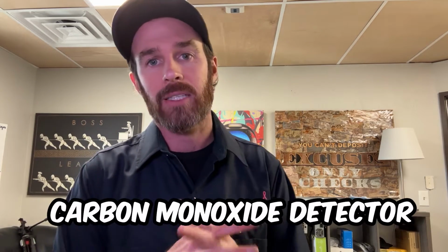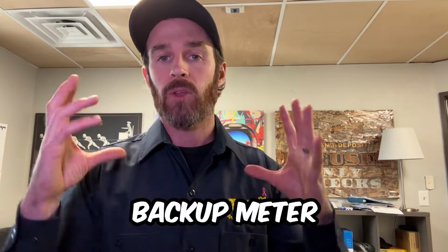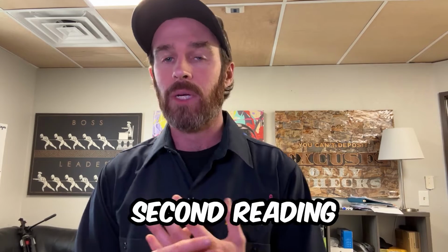And the way to detect this is with a simple meter like the Fluke CO-220 or the UEi carbon monoxide detectors. And if you ever get a meter that picks up carbon monoxide, it is good to check it with a backup meter. And the reason is that meters, like all pieces of technology, can put out false readings from time to time. So it's important to get a second reading.